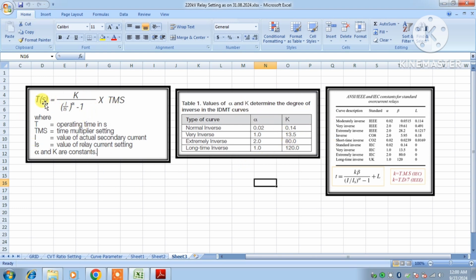Operating time equals K divided by (I by IS) to the power alpha minus 1, multiplied by the time multiplier setting. The TMS will be given in the relay setting file. IS is the setting current, I is the fault current, and K and alpha are constants. The K and alpha values vary according to the selection of different curves. It is useful during relay testing and commissioning.